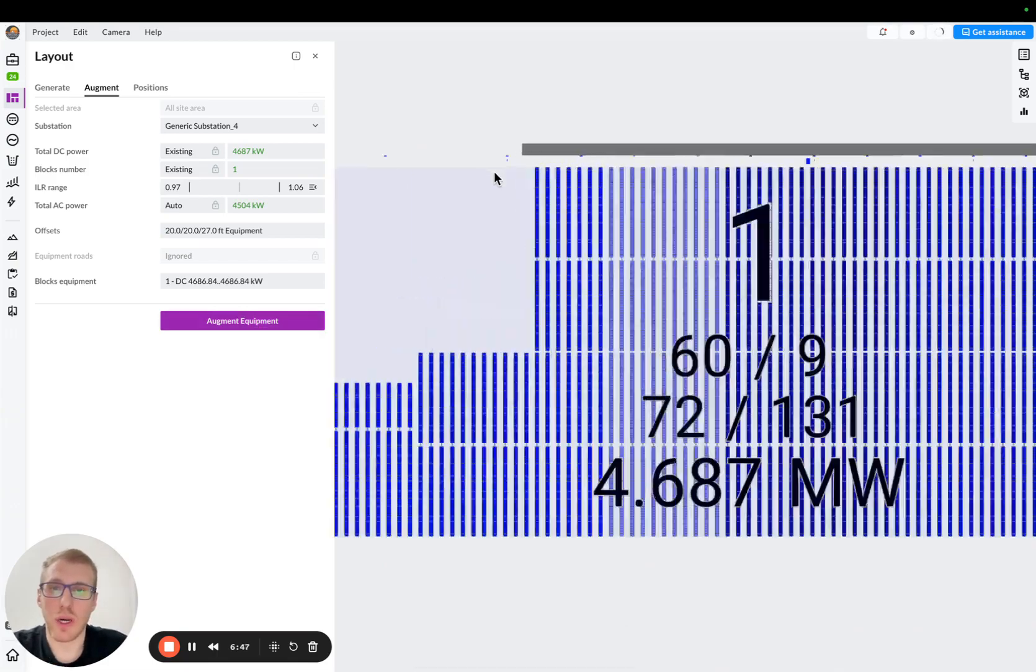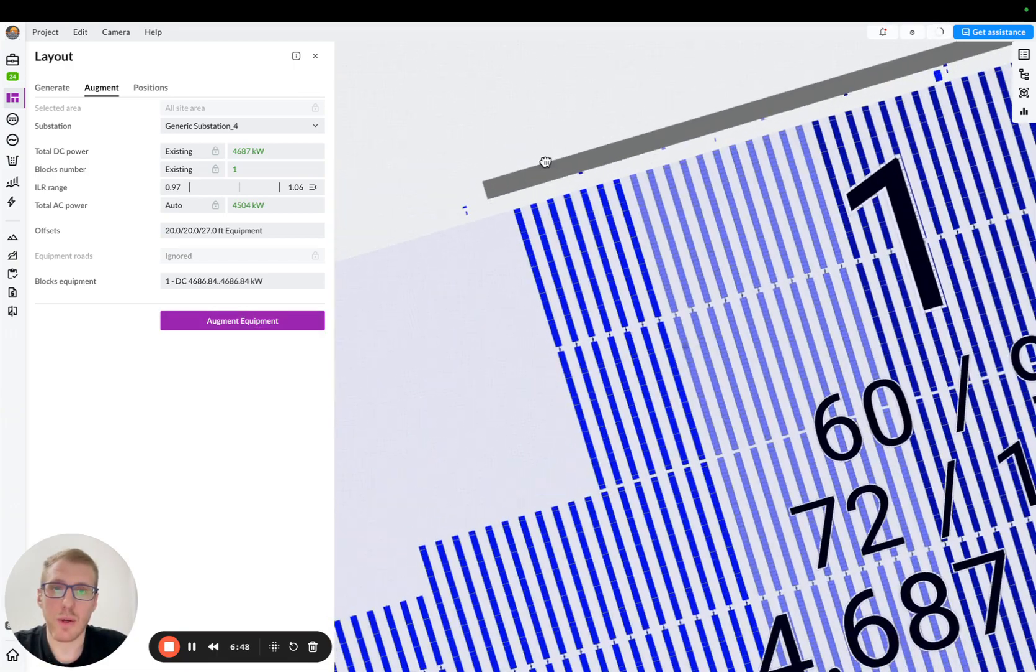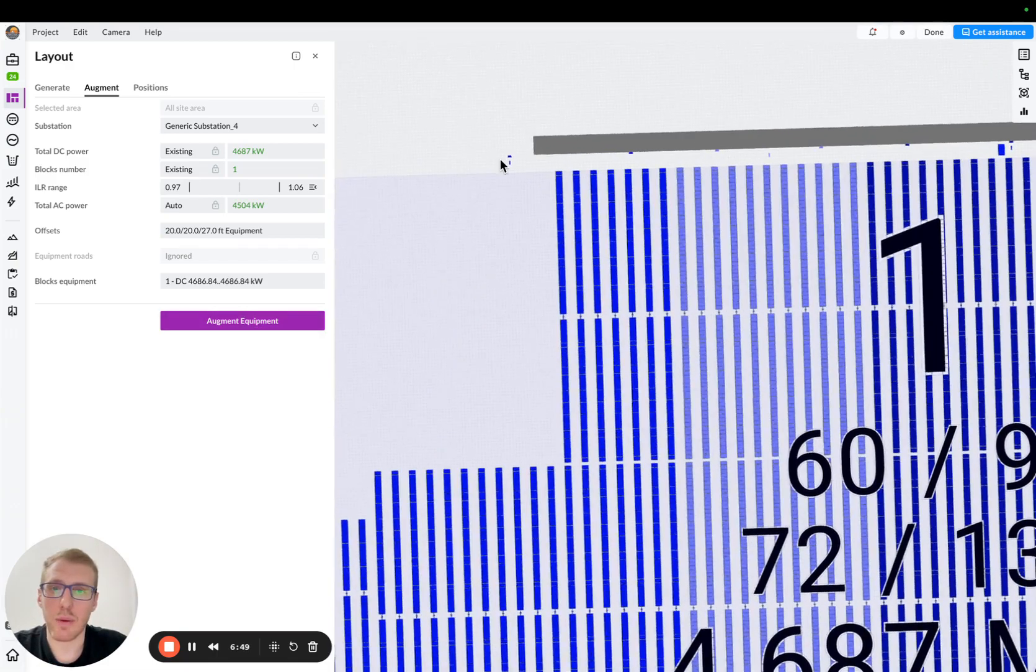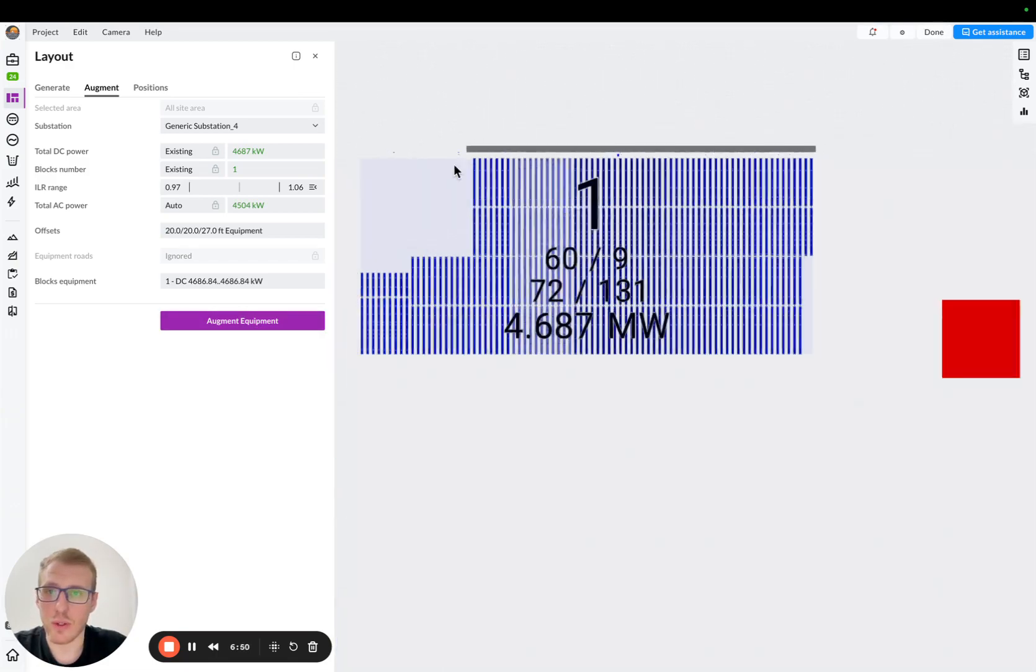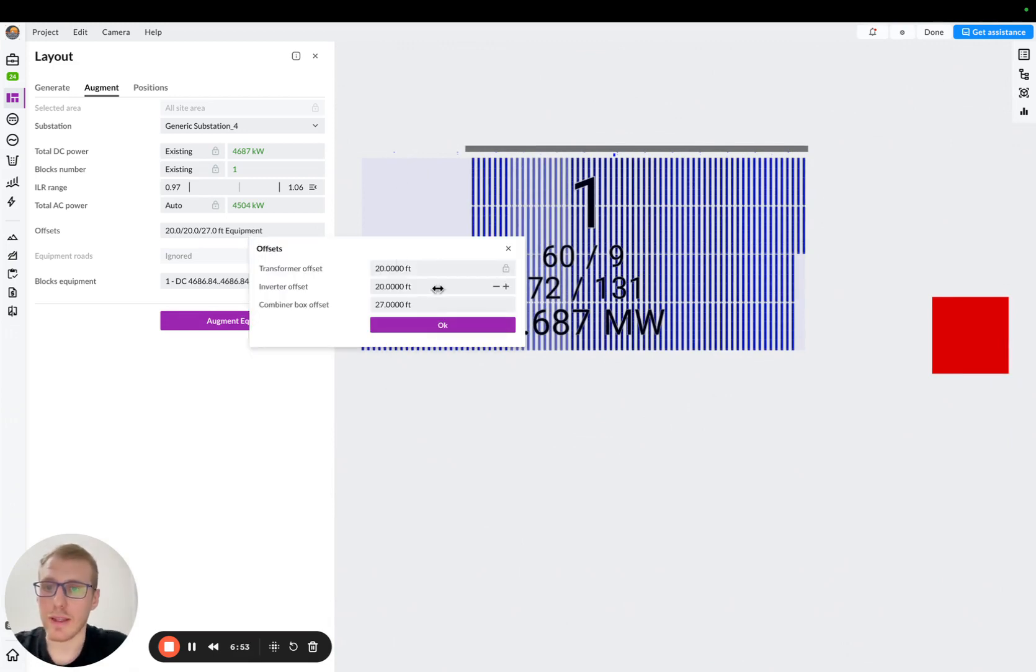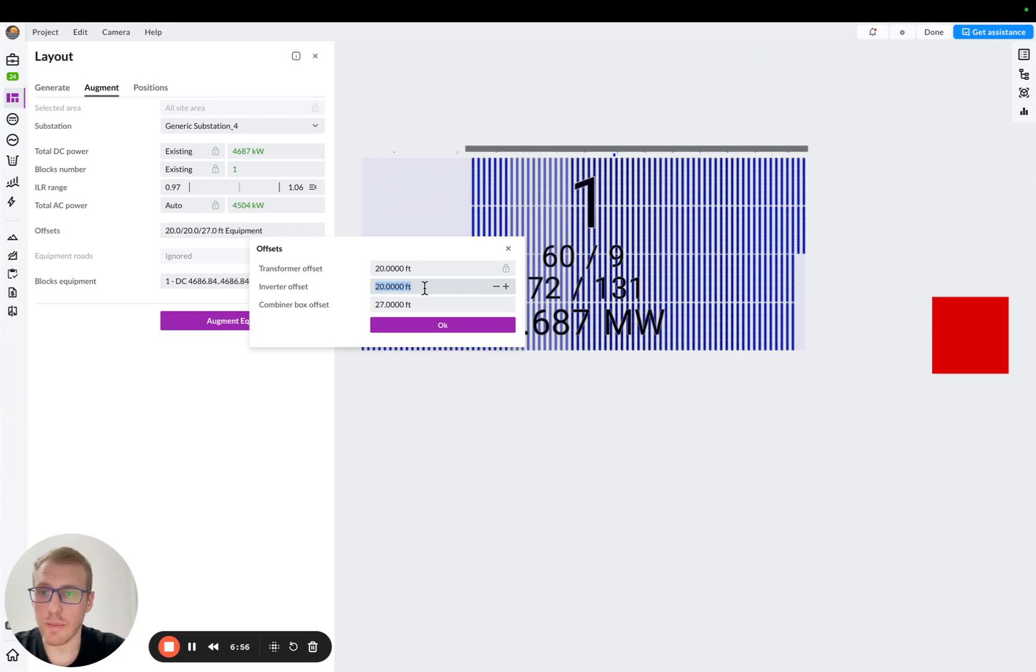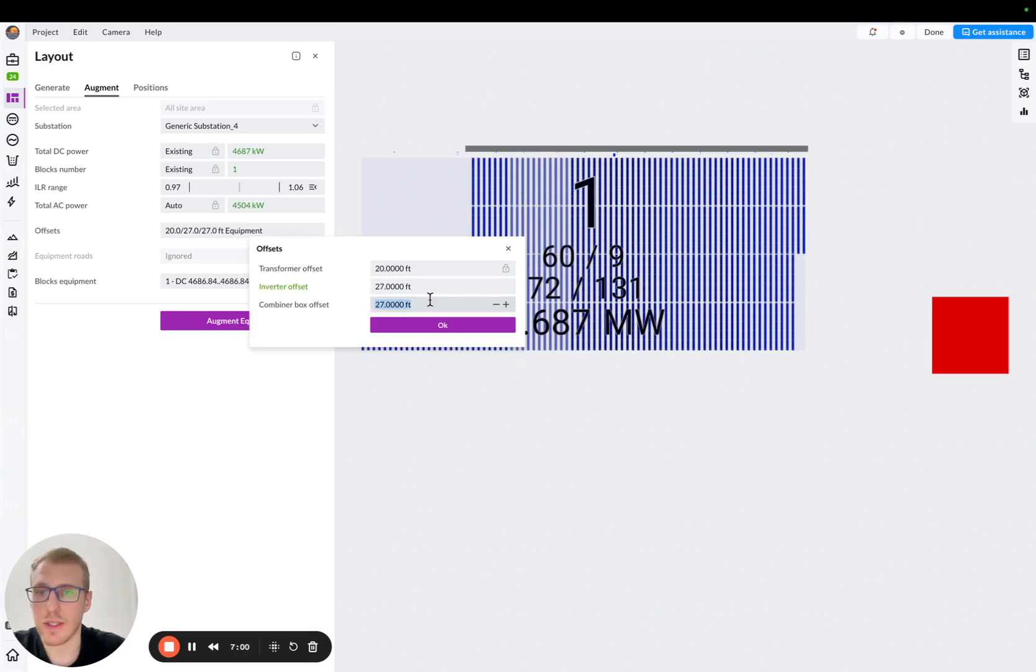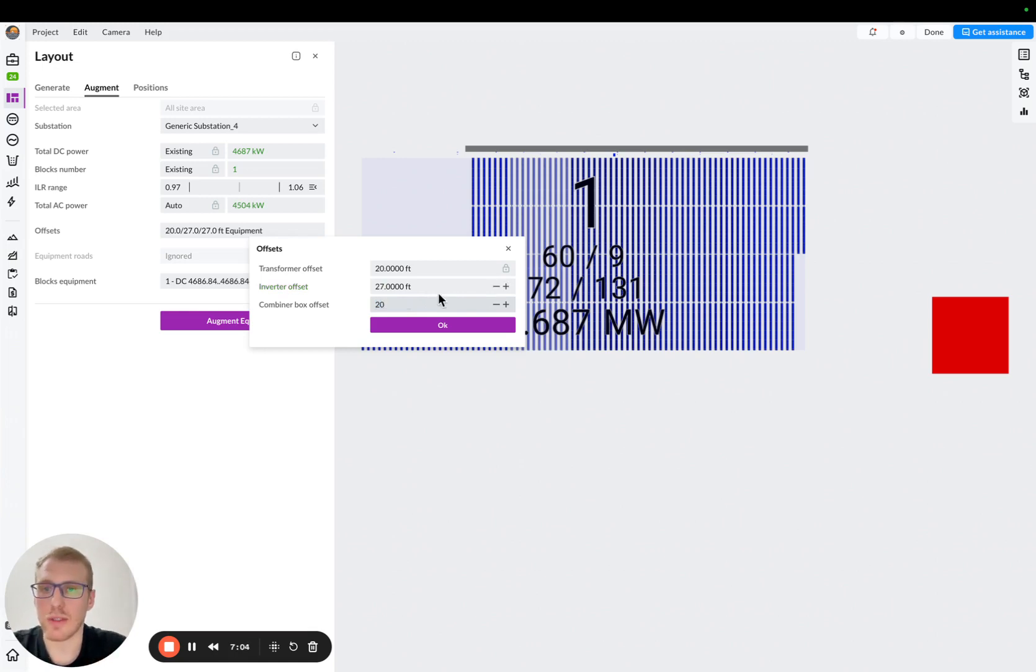And let's see what's going to change. So after we augmented our equipment, I would actually recommend also to make sure that offsets are correct, okay? In a string inverter scheme, I would actually make inverter offset a bit bigger, let's say 27 feet from the center of the rod, and then combiner box offset 20 feet.